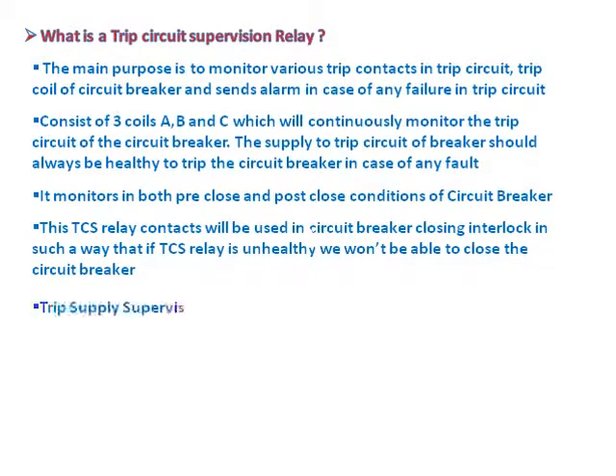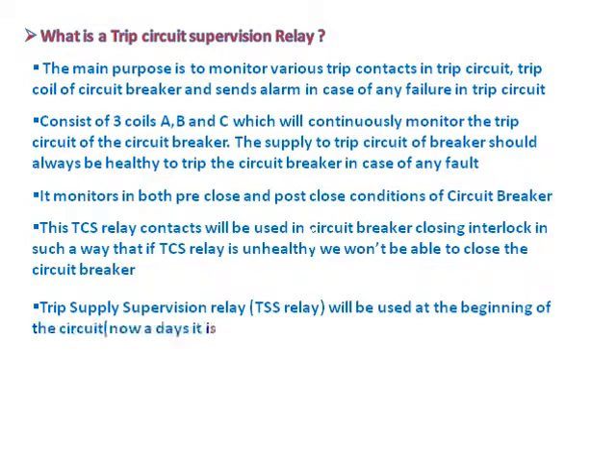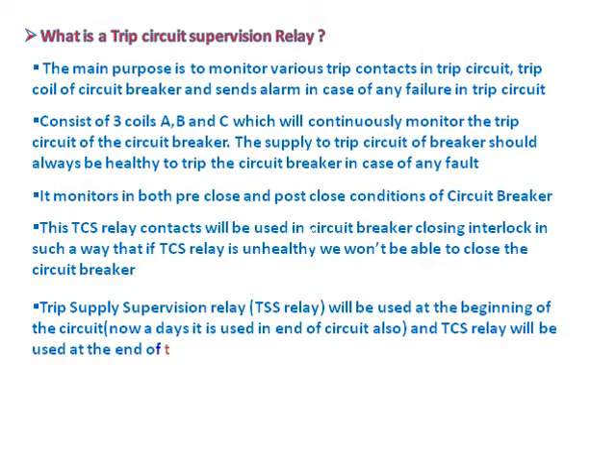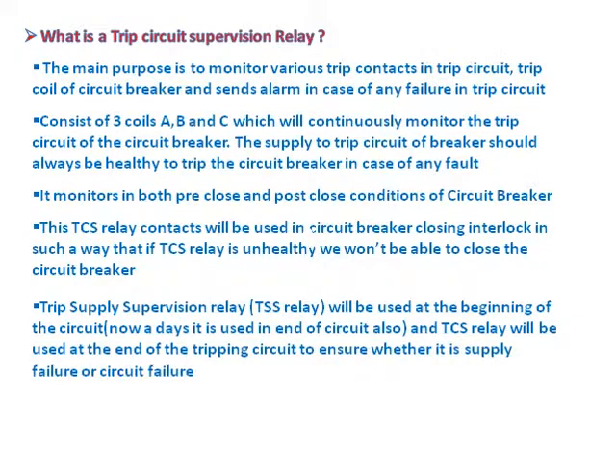The Trip Supply Supervision Relay, or TSS relay, will be used at the beginning of the circuit. Nowadays it is also used at the end of the circuit, and the TCS relay will be used at the end of the tripping circuit to ensure whether it is a supply failure or a circuit failure.